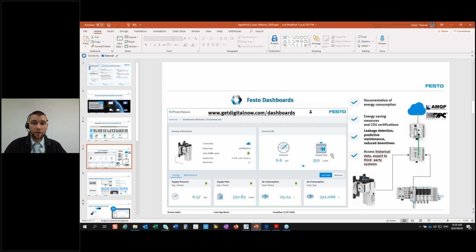100%, Martin. Thank you, that's a very, very good question. The energy efficiency modules that we have at the moment are called MSE6 E2M. If you want, I'll definitely send you some info on them afterwards. Basically, it's a combination unit of an on-off valve, a pressure sensor, a flow sensor, and a field bus node. You can connect that into either your existing field bus system or your existing PLC network, or you can create a standalone system.